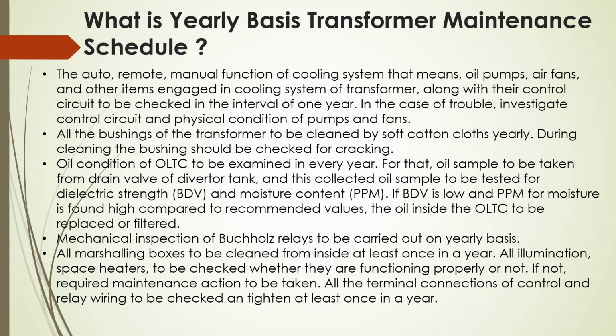Mechanical inspection of Buchholz relay to be carried out on yearly basis. All marshalling boxes to be cleaned from inside at least once in a year. All illumination space heater to be checked whether they are functioning properly or not. If not, required maintenance action to be taken. All the terminal connections of control and relay wiring to be checked and tightened at least once in a year.